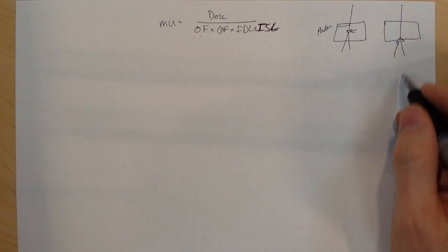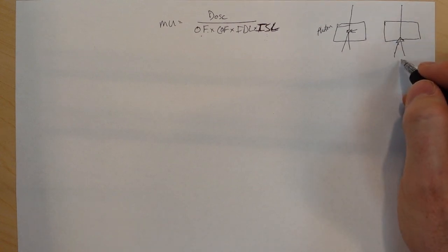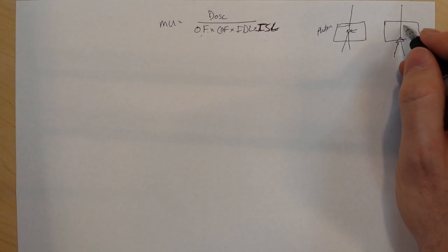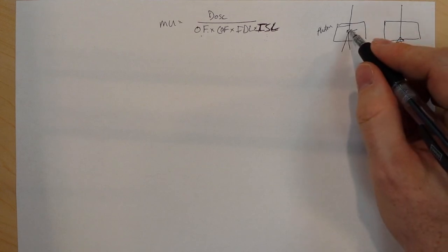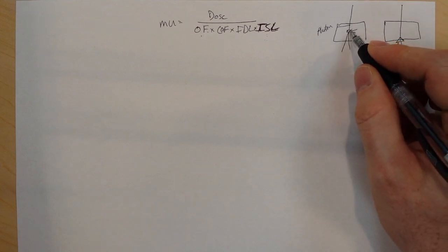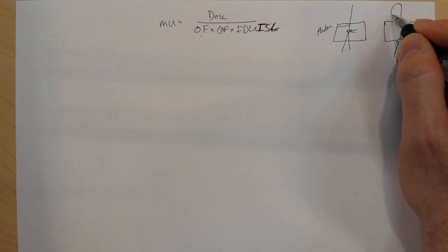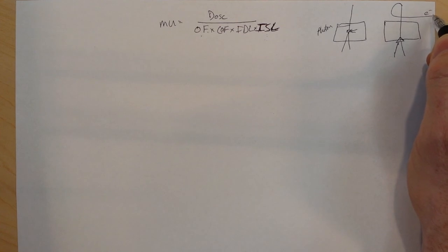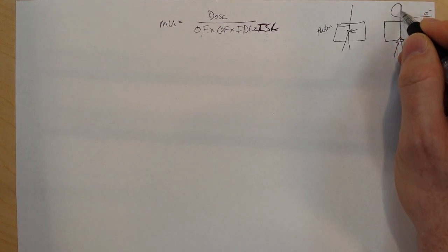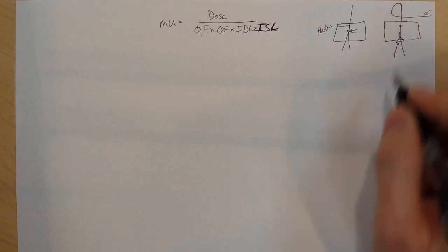So you might say, when doing an inverse square law, well, what's my SSD, my source to skin distance? Here's my source. There's no source here. My electron beam comes out of the accelerator through the bending magnet and then down. There's no particular source.